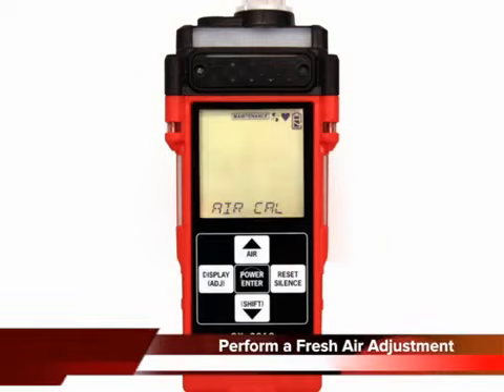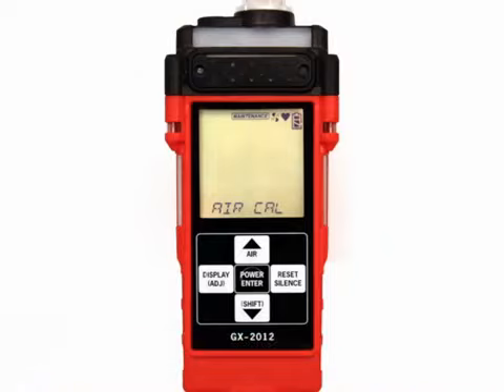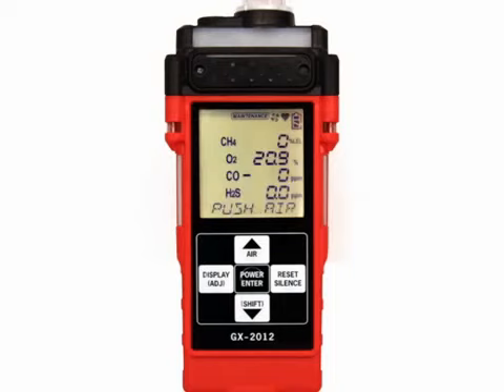Find a fresh air environment, an environment of normal oxygen content, 20.9%, that is free of toxic and combustible gases. When the AirCal screen is displayed, press and release the Power Enter button. A screen appears that prompts you to press the Air button by displaying the Push Air message at the bottom of the screen.